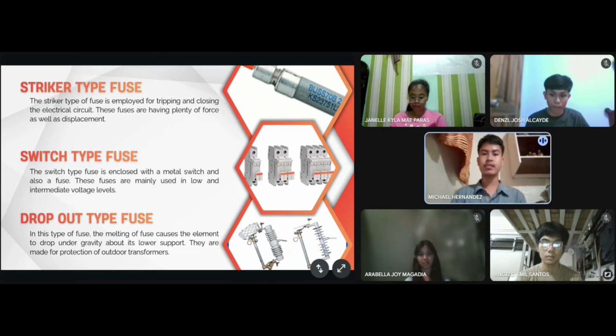The next one is the dropout type fuse. It's a special kind of fuse commonly used in outdoor electrical distribution systems, especially on power poles and transformers. It's called dropout because when the fuse blows, the fuse holder actually drops or swings open, giving a clear visual indication that the fuse has operated.